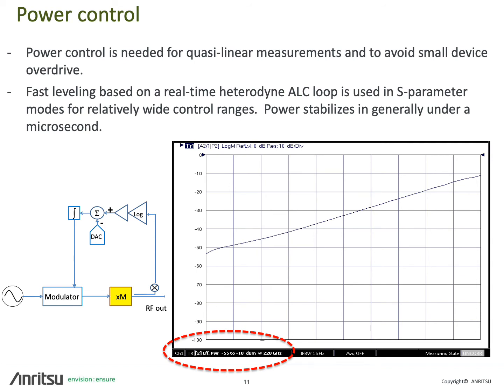As shown in the previous block diagram, we offer electronic ALC control. This ALC circuit is a real-time heterodyne ALC loop and can get down to the minus 55 dBm range, which is quite useful when characterizing active devices that need to be well within the linear region. Often the linear region can be far below minus 30 dBm, so having this amount of power control when characterizing active devices is quite useful.